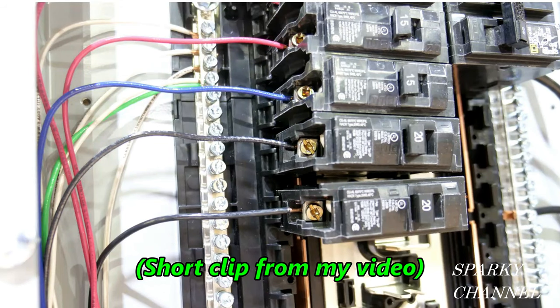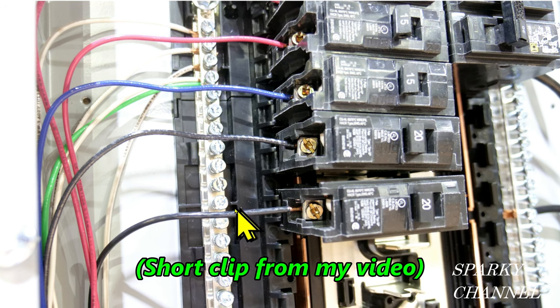Here are some circuit breakers in the main panel. This circuit breaker is 15 amps. This one is 15 amps. This one is 20 amps. And this one is 20 amps. Now let's look at the wires going to these circuit breakers. Notice this one is thicker than these other three. Well, this is a 12 gauge wire. This is a 14 gauge wire. This is a 14 gauge wire. And this is a 14 gauge wire.